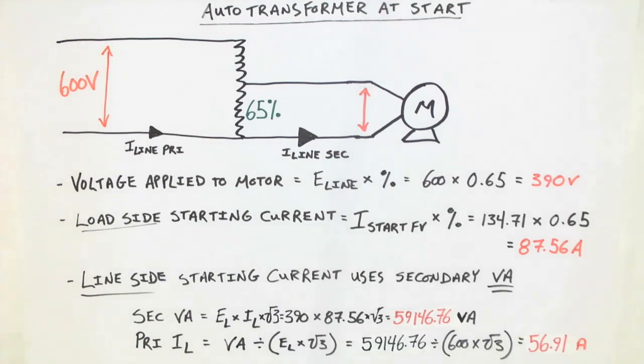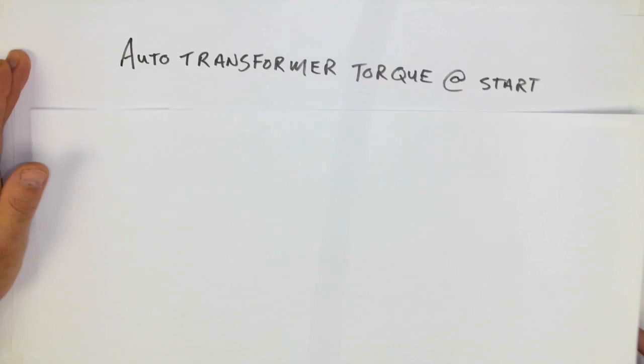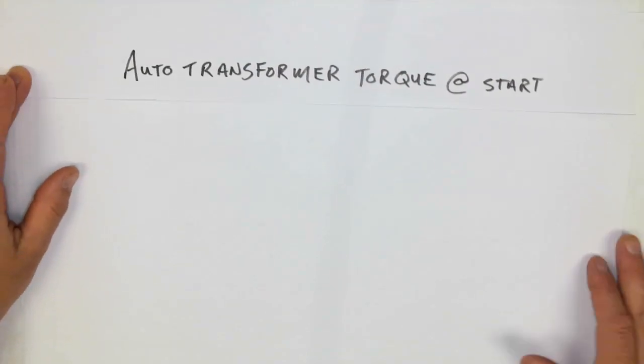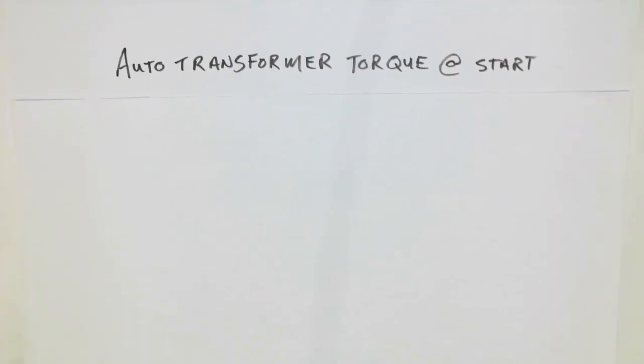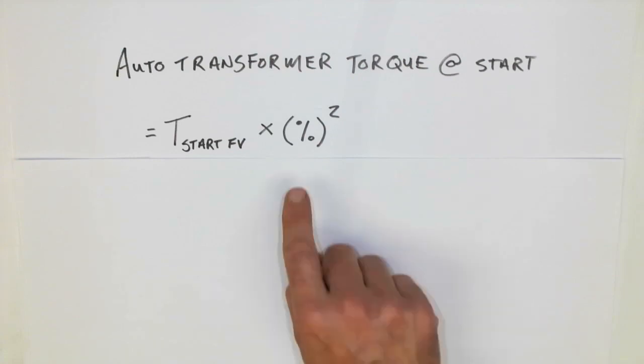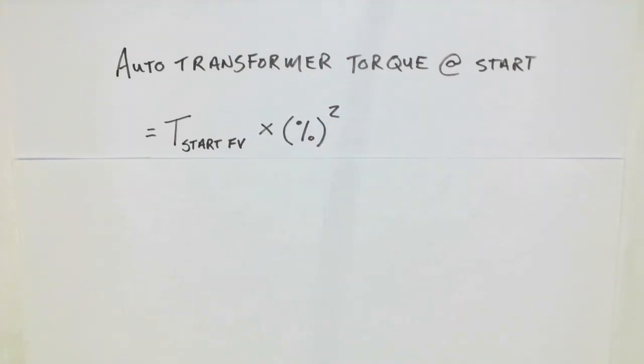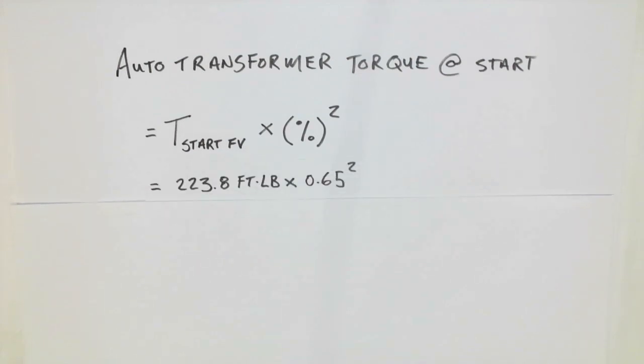Let's take a look at what the value of torque would be for this starter. The autotransformer torque at start is calculated in exactly the same way as what we saw with the primary resistance. T start at full voltage multiplied by the percent squared, the percent given in the starter literature. So 65% voltage is what we're achieving, which means the total torque is 94.55 foot-pounds.